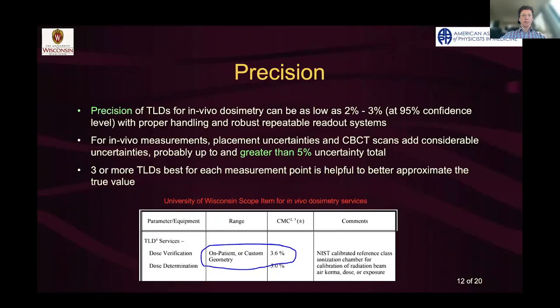The precision of TLDs can be very good. If you have proper handling and a robust, repeatable system, they can be as low as 2 to 3%, and that's with a 95% confidence level. For in vivo measurements, there are a lot of additional uncertainties, such as the gradients on the skin, if you have a cone beam CT, things like that. So overall, the uncertainty of the whole procedure is about 5%, and can be greater. But really the TLDs themselves are pretty low uncertainty.